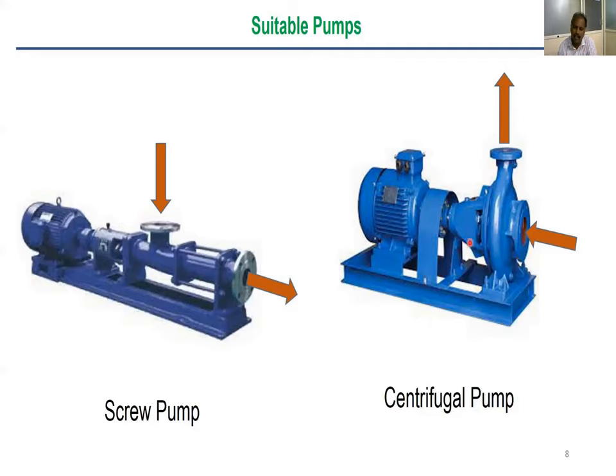For very high flow rates, centrifugal pumps can be used. In these, an impeller rotates with suction on one side and delivery upward. At pilot scale with 40 mm diameter pipes, the progressive cavity pump is preferred. At industrial scale with 200 mm diameter pipes, particle sizes of 2–3 mm won't block the impeller, so centrifugal pumps become suitable. For fermentation, centrifugal pumps are also appropriate since after glucose is fermented to ethanol, viscosity decreases from 50–100 centipoise down.